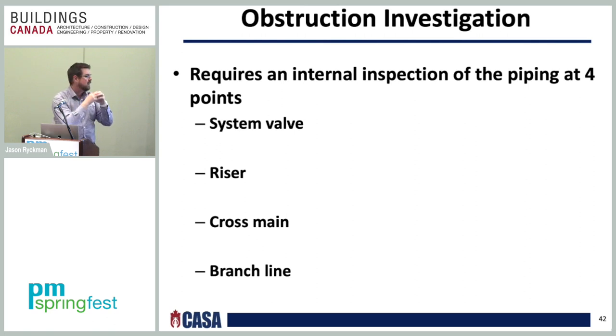It's the bigger pipe, which I call that. I always go by human anatomy whenever I'm talking about a system. Your water supply is your heart, your main is your artery, and your branch lines are kind of your little veins. So I always try to give an analogy on that. So that's the difference between that. So system valve, riser, cross main, and branch line. Those are the four internal inspection points that you have to do whenever you're doing an obstruction investigation.